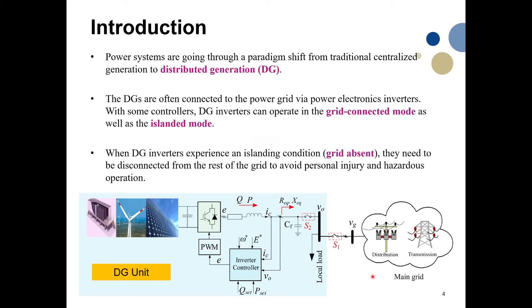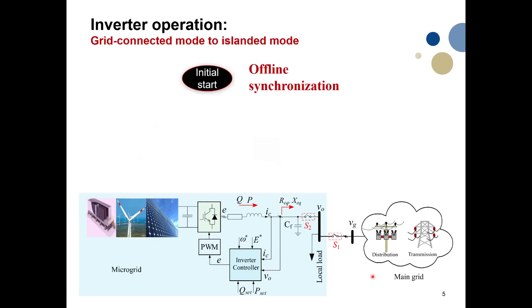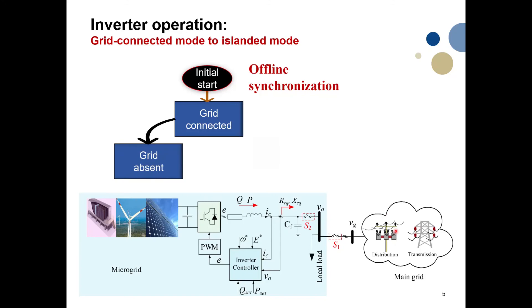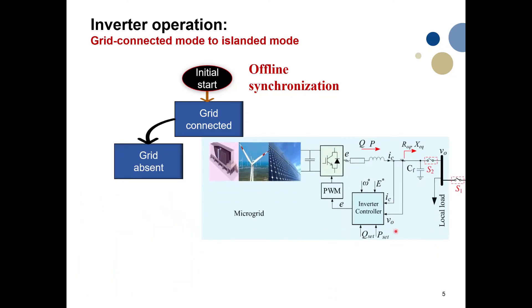To achieve this seamless operation, we need to address several control challenges. First, let's review how it works. We have this inverter-based microgrid, and to connect this inverter to the grid, we first perform offline synchronization before turning on the PWM — usually applying a PLL or other methods. When offline synchronization is complete, we connect to the grid for grid-connected operation. When the grid is absent, we need an islanding detection technique to detect that the grid is absent.